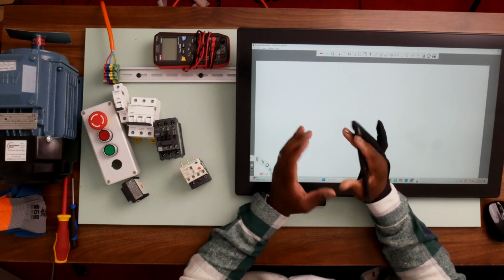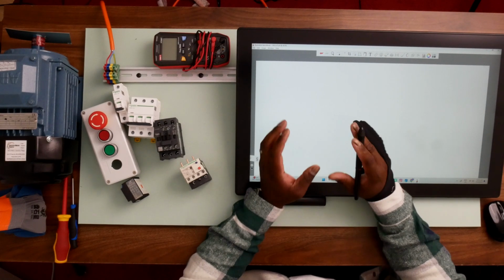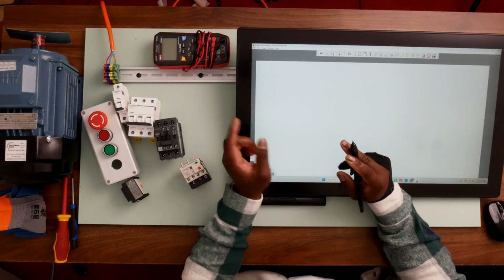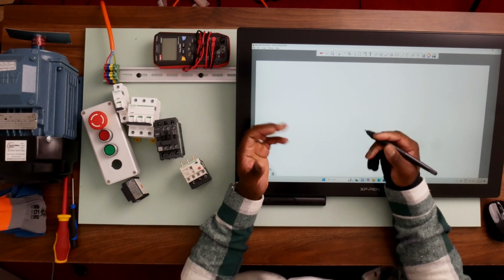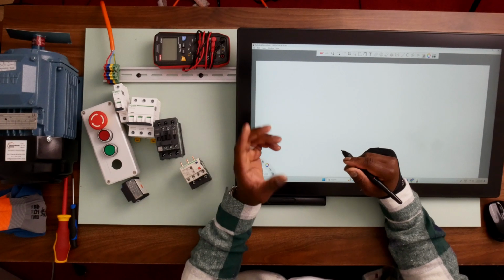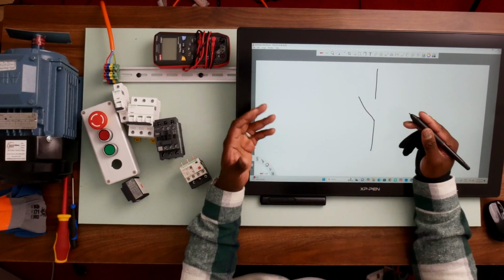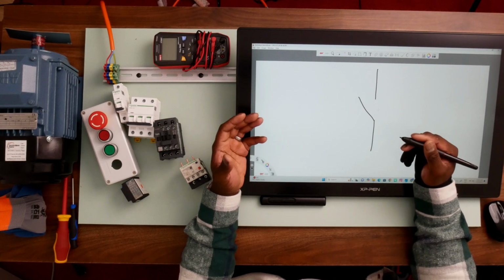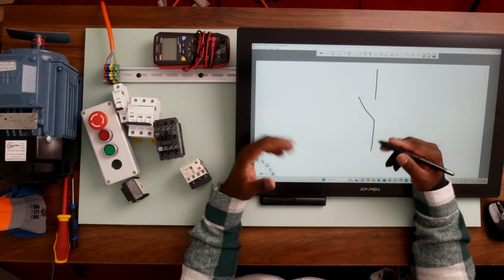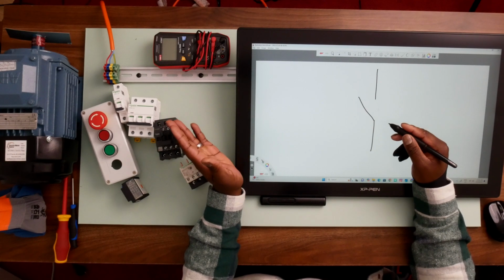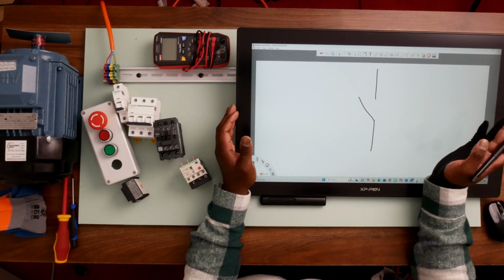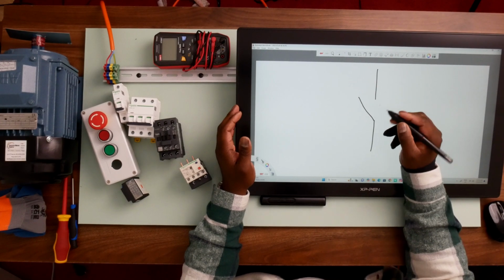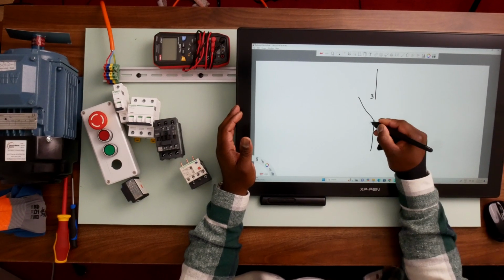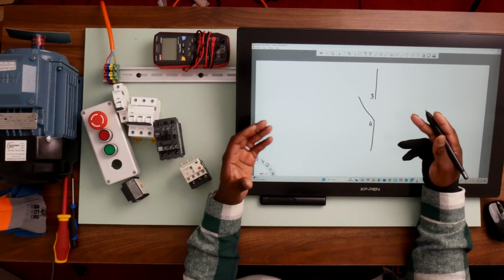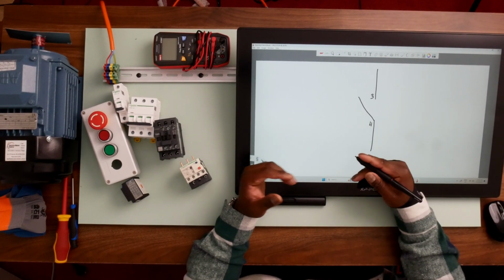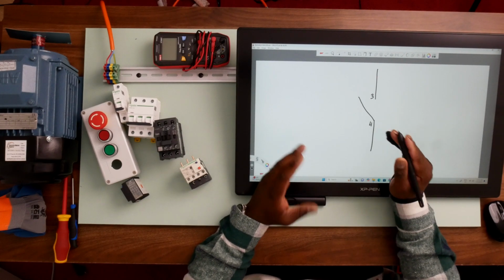And the last push button in our direct online starter is the start push button. The start push button, just like the stop push button, is also a momentary contact push button, and it's a normally open contact. One thing you always have to remember is when you are drawing symbols according to the IEC 60617 standard, your normally open contacts will always be facing to your left, and your normally closed contacts will always be facing to your right. So this is the general symbol for a normally open contact, and it's labeled 3 and 4 most of the time, or any combination of numbers ending with 3 and 4. So this is a simple normally open contact.